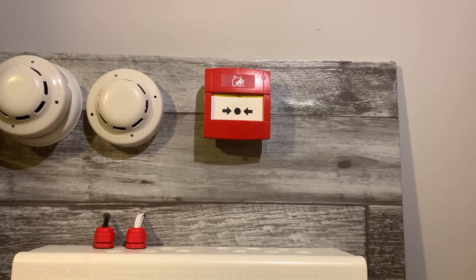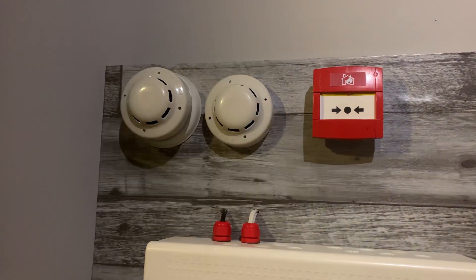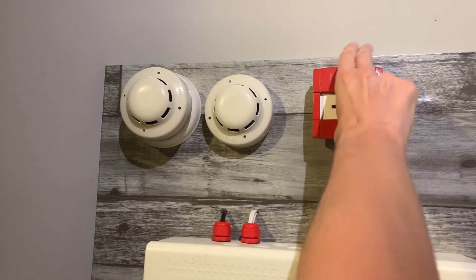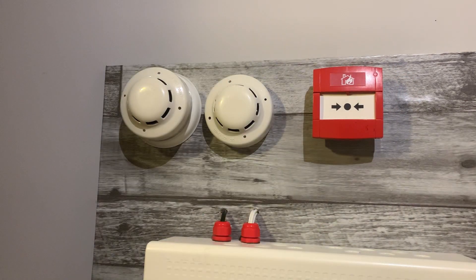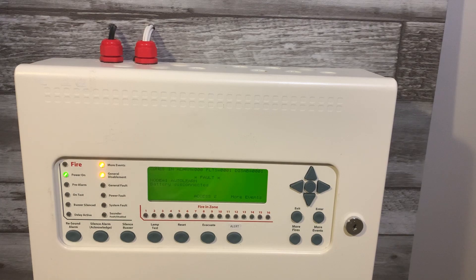I'm going to give the call point a quick test — I'll just press it because I think it's easier. There we go. So yeah, it's a white flash, a white VAD. I can't change the tone on it without the software, which is one thing with Kentec that's a bit annoying. Now let's give the panel a reset — it's just wired into the CNT input. The panel resets the call point, and there we go.